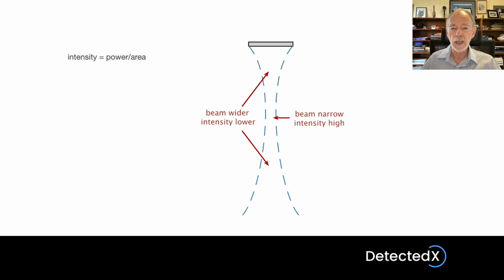This is particularly interesting to us because it works in reverse. If the machine can do things which make the intensity at a particular depth the maximum possible, the highest possible intensity, that's going to guarantee that the beam is as narrow as the machine can make it at that particular depth. So that's basically how focusing works. At the depth you want the beam to be focused, the machine is going to strive to make the intensity as high as possible, and that's going to guarantee that the beam is as narrow as possible.